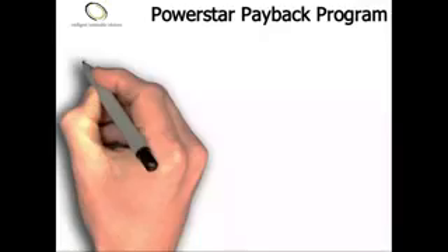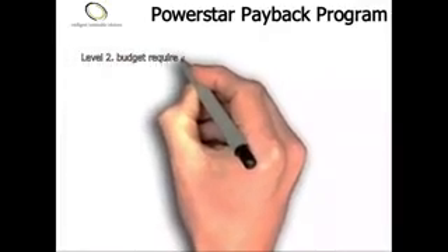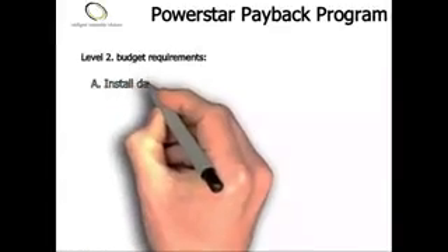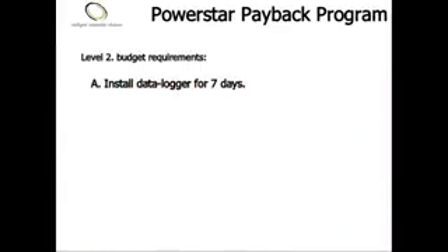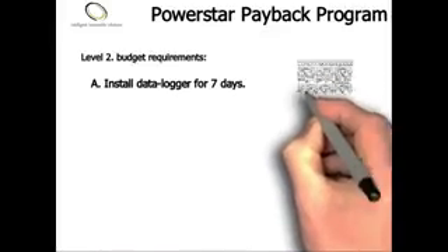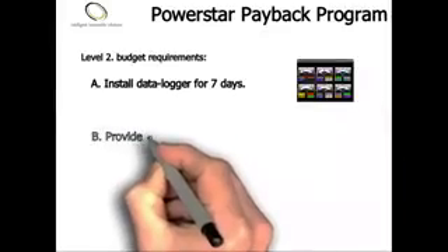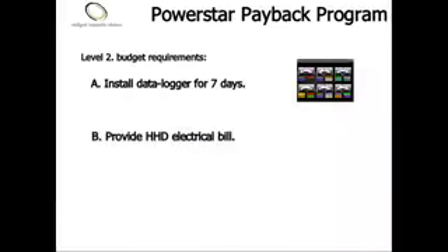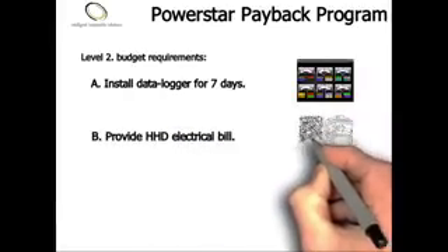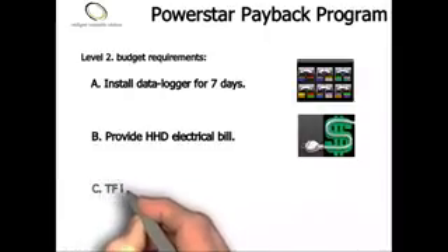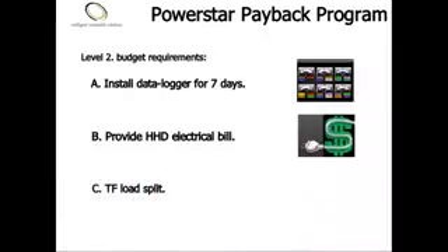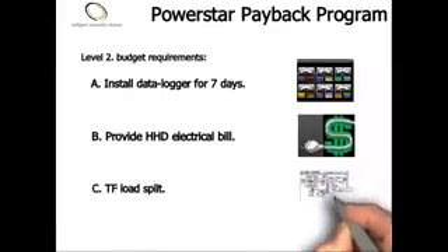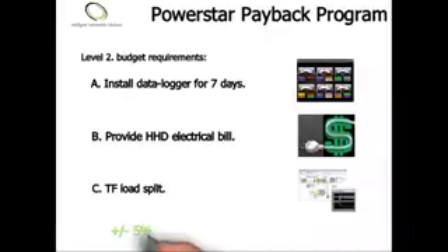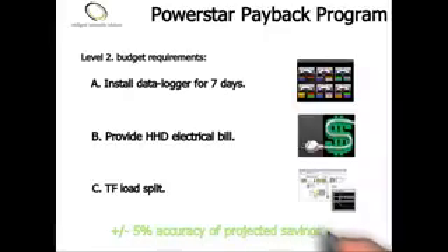To achieve Level 2 budget requirements, we should follow the next steps. A. We will install a data logger for approximately 1 week. Some sites can provide the voltage profile, which is even better and speeds up the process. B. Provide us the half-hour data and a copy of the electrical bill. This helps us understand the site historic consumption and how that consumption applies to specific transformers on site. C. Understanding how each load is distributed across the relevant transformers on site, along with the year of manufacture and/or the efficiency of the transformer is also required. This increases the accuracy of projected savings down to plus or minus 5%.